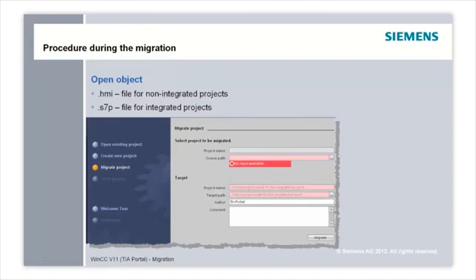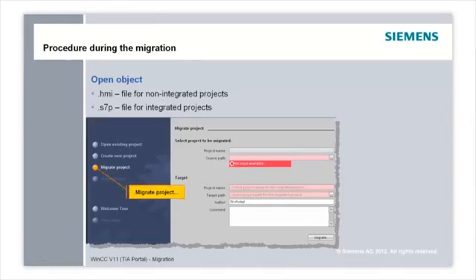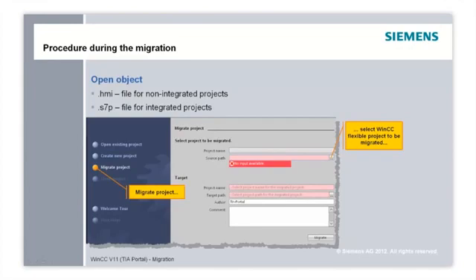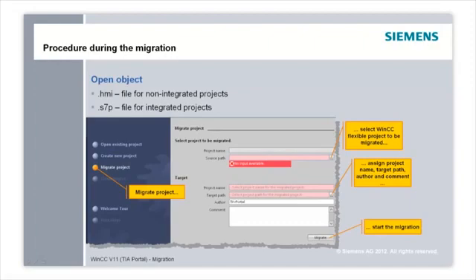How to realize a migration? You can migrate WinCC Flexible standalone projects to WinCC version 11 as well as WinCC Flexible projects integrated in Step 7. In the WinCC version 11 portal, you choose the action Migrate Project. Then you specify the source path of the Step 7 or WinCC Flexible project, as well as the target path for the migrated project. Press the Migrate button to migrate the project to WinCC version 11.